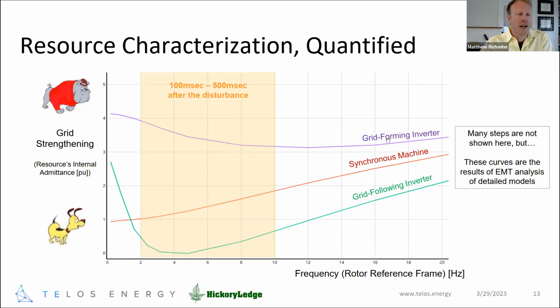And then finally, with grid forming inverters, an example grid forming inverter shown in purple. One of the things you notice is first, the admittance value, the grid strengthening behavior is significantly higher than both the grid following inverter, which we would expect, but also even the synchronous machine example in this case. Second, the response is relatively constant across this portion of the frequency domain.